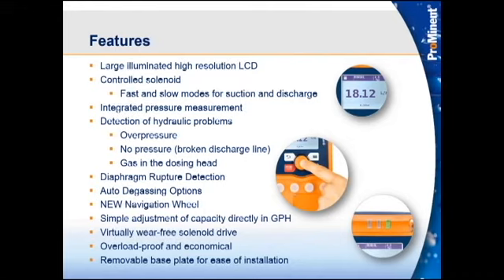Okay, I will tell you that the center line of the head is slightly off from the Gamma L. The pump is slightly higher. We're only talking fractions of an inch. It shouldn't be that much of a problem. Most of our skids that leave here with smaller solenoid pumps are plumbed with tubing.